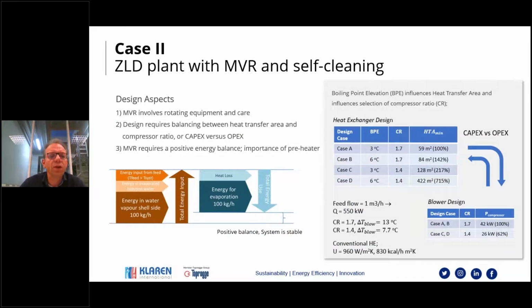Zooming into three very important and critical design aspects. The first one is, I already showed you some pictures of the compressors. So an MVR involves rotating equipment, where the roots blower might be a bit more simple, having rolling bearings. Lubrication is there, but is less important. Especially the centrifugal compressor is rotating equipment and really requires careful care. Meaning that you need to monitor its performance. You need to be careful that vibrations are in order, that you do not get deposition of dirt on the blades of the compressor. So you really need to take care also to improve the lifetime of the compressor. And in case of a damage, you really talk directly about a lot of money. So something not to forget. MVR with rotating equipment requires care.